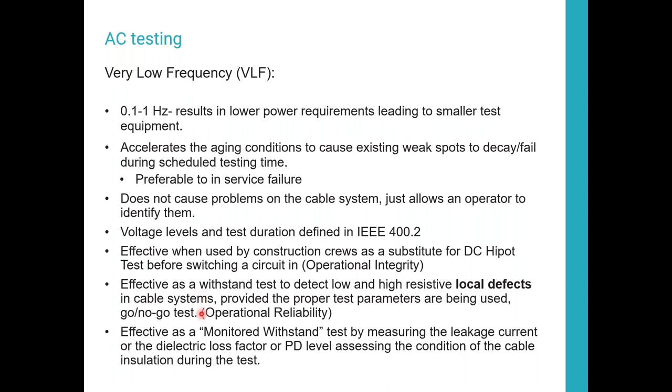It's effective as a withstand test to detect low and high resistive local defects in cables and in cable systems, provided the proper test parameters are used. Basically, it can be used as a go, no-go test. Set up a threshold. If my cable withstands 1.5 to 2 times nominal rated voltage, we're good. I don't need to know that it's going to break down at 5. Since it won't break down at 2 times my nominal voltage, I don't have to worry about it.